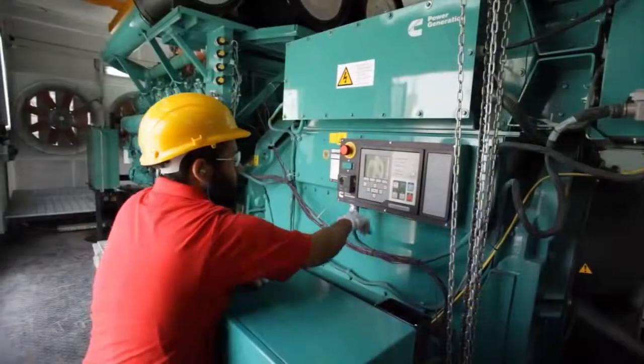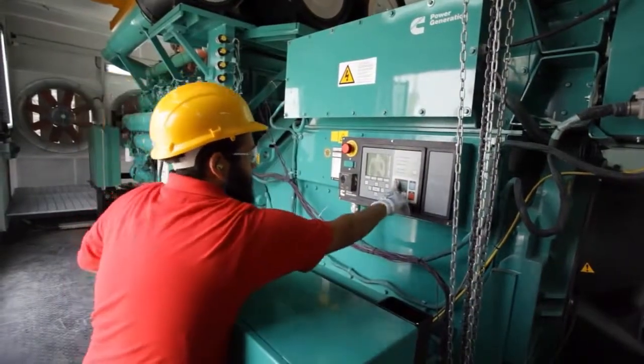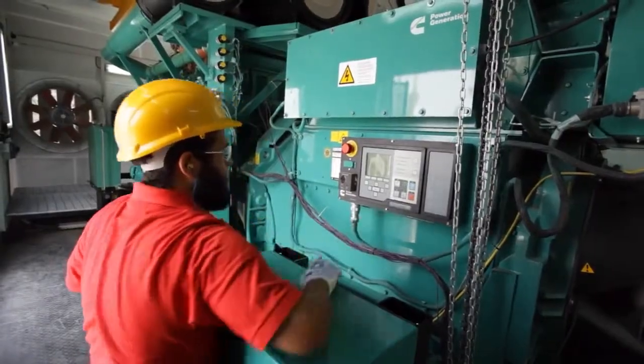Upon running the test at a 2.0 rooftop level, the unit performed properly. We have so far not found anomalies with the unit, the test fixture, or the isolation system. It ensures that the unit will survive an earthquake and will be able to run afterwards.